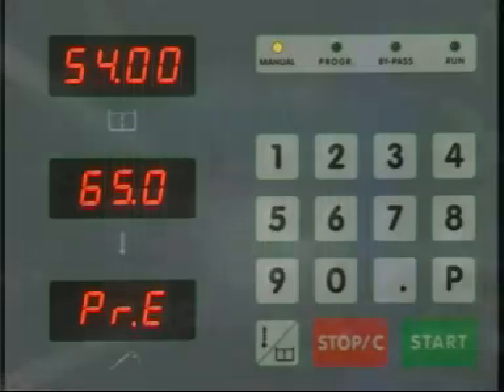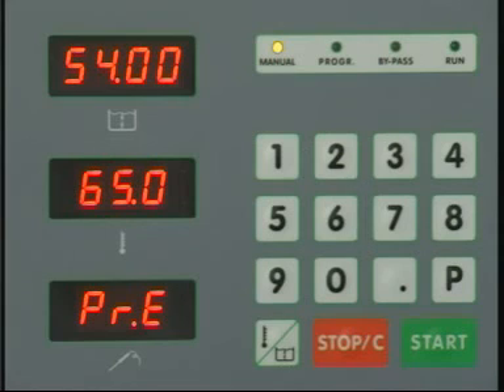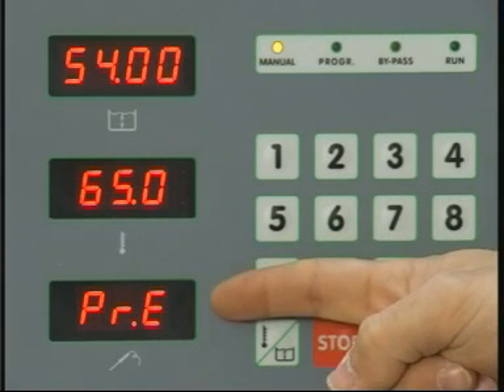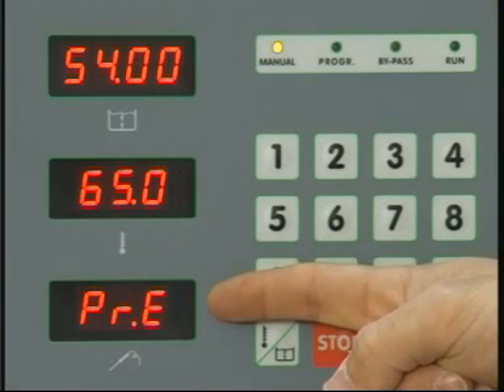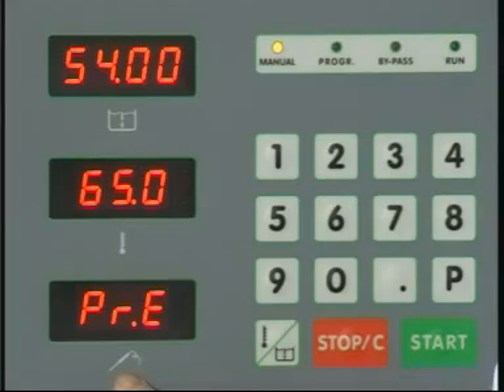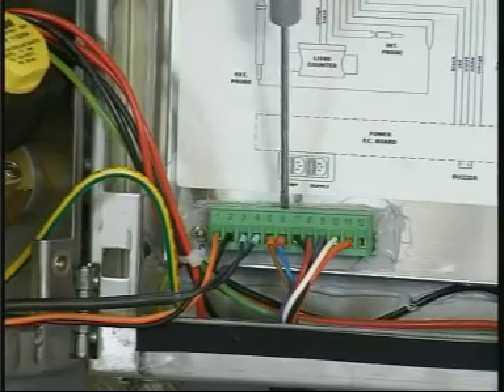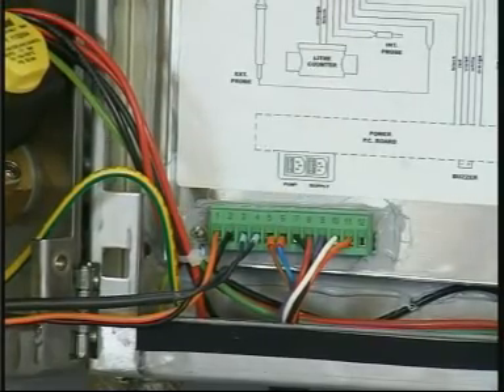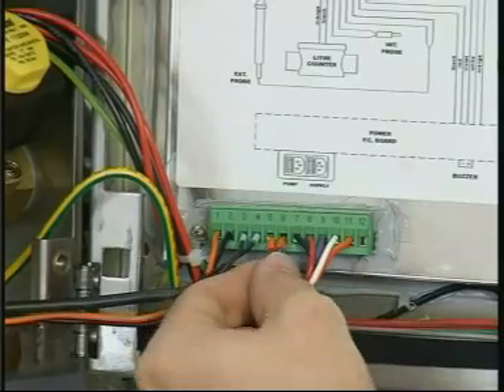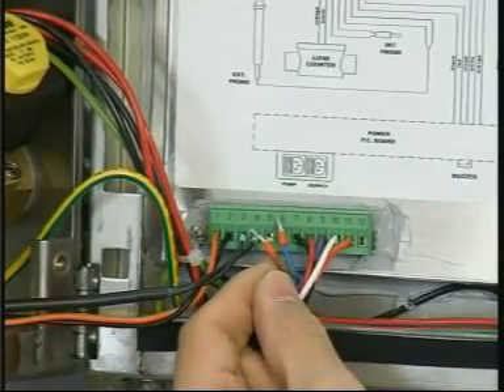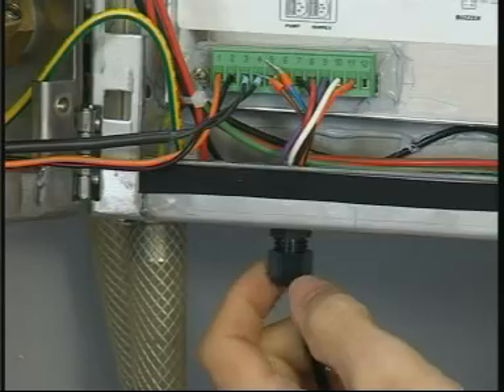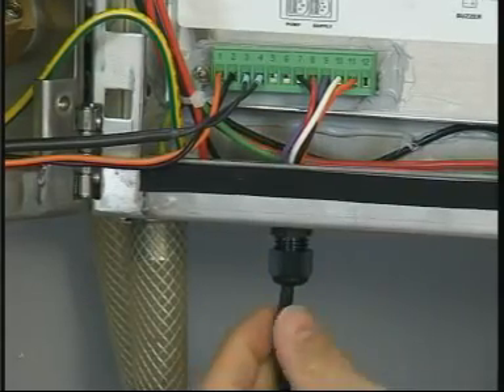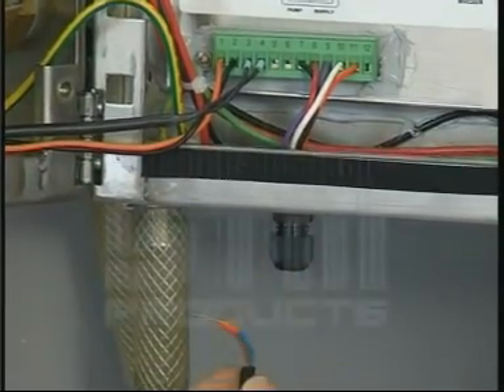External probe error. If a fault of this nature appears, showing the message appearing only on the lower display, this means that the external temperature probe is broken or badly connected. Replacement of external probe. Switch off the supply to the machine. Unscrew terminals 5 and 6 as shown. Unscrew the cable clamping and extract the probe cable.